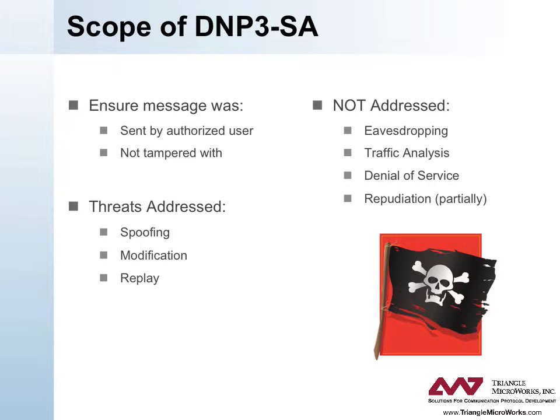However, DNP3 Secure Authentication does play well with encryption methods, such as TLS, on IP networks. DNP3 Secure Authentication also does not protect against traffic analysis — the ability of an attacker to determine what a utility is doing with a remote device by watching the pattern of message traffic. Lastly, it does not protect against denial of service — an attacker transmitting so many valid or invalid messages at a remote device that it is made unavailable to valid users. Denial of service attacks are best dealt with by an intervening device like a proxy server or firewall that can filter unwanted messages.